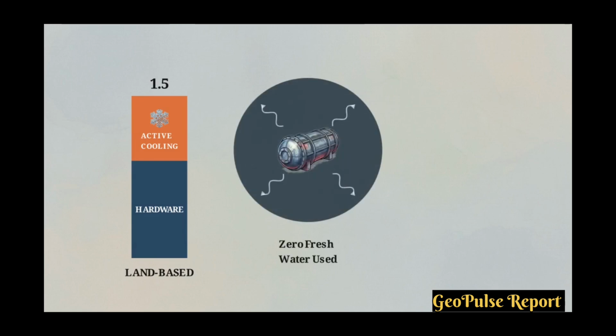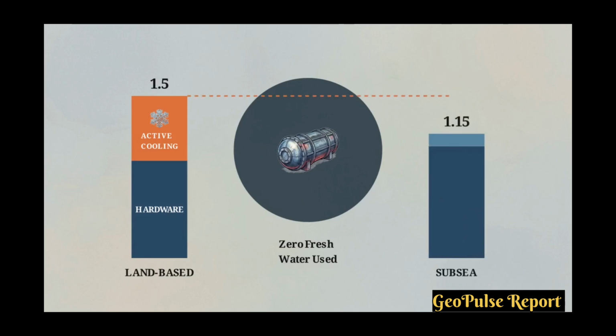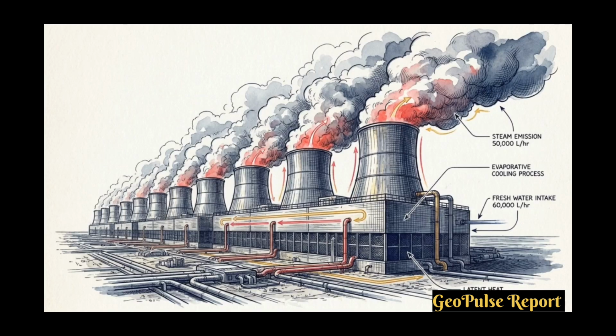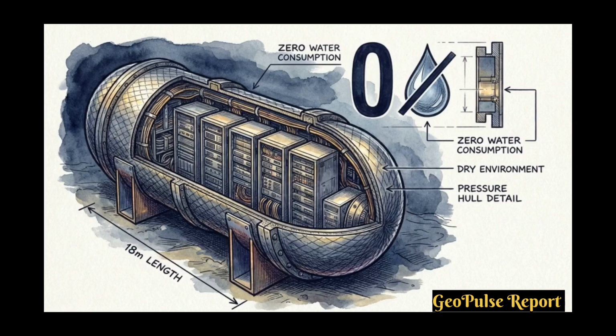Enclosing servers in subsea capsules lets thermal load passively dissipate into the ocean. This compresses PUE below 1.15, reducing cooling to 10% of total energy use. Terrestrial facilities also evaporate millions of gallons of fresh water annually to manage heat. The subsea modules consume zero fresh water.